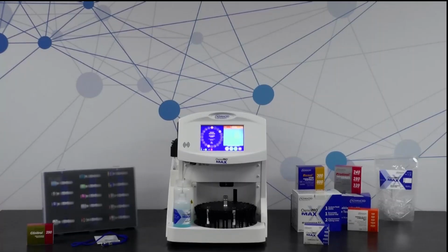Like, for example, if your QC is out, maybe because, and by the way, strongly advise against this, every 290 should be single use only, especially with this instrument. So strongly advise against this. But for example, if they had a 290 sitting around that they tried to reuse, maybe the QC was out because of evaporation, it will still let you run a new vial of 290 to rerun the QC, but it won't let you run any patient tests until your QC has passed. So that's how that feature works.